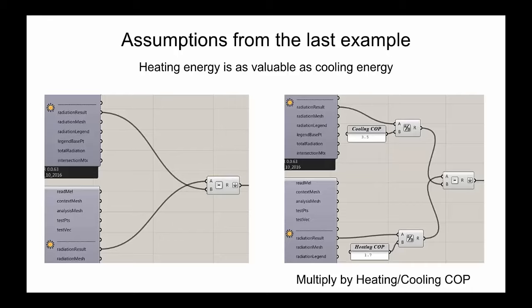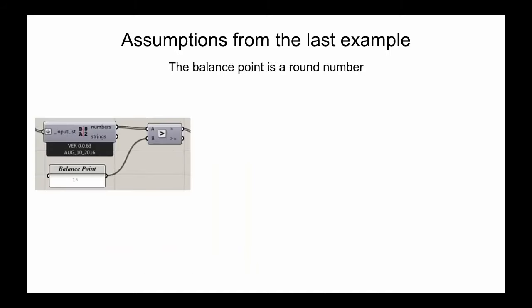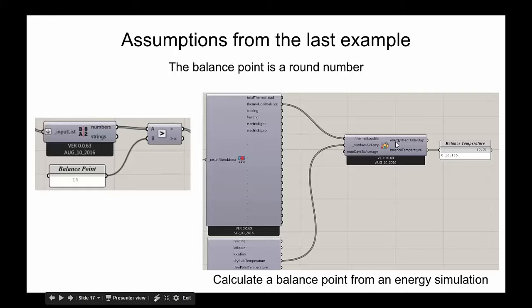You can start with raw assumptions and refine your studies as you better understand your HVAC systems. Finally, another assumption was that I used my intuition to set the balance point at 15°C. Intuition is okay for a rough start, but you can actually get a balance point from an energy simulation using the Honeybee Calculate Balance Temperature component. I ran a test box model for an office in Boston and got 16°C — a bit higher. These are not meant to be hard and fast rules; they're things you customize to answer your unique questions.